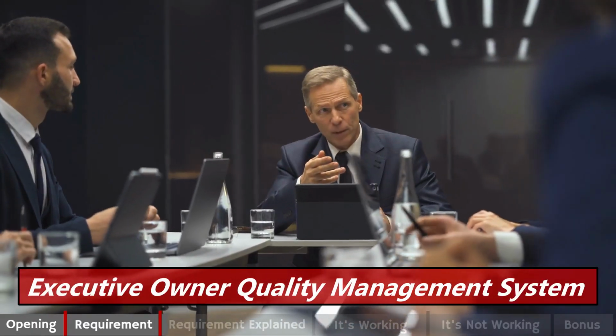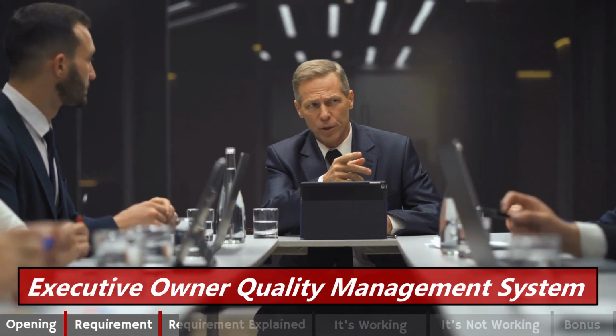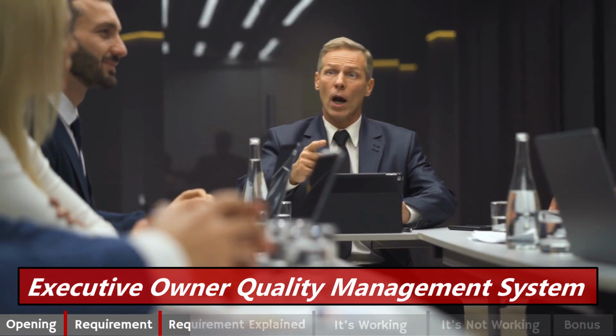5.5.2. Management representative in 5 words. Executive owner quality management system. Top management must appoint a management representative. That management representative has 3 key responsibilities. First, they are responsible for implementing an effective quality management system. Second, they need to report on the performance of that quality management system to top management. And then finally, they have to communicate the importance of the regulatory requirements and the quality management system requirements throughout the organization.